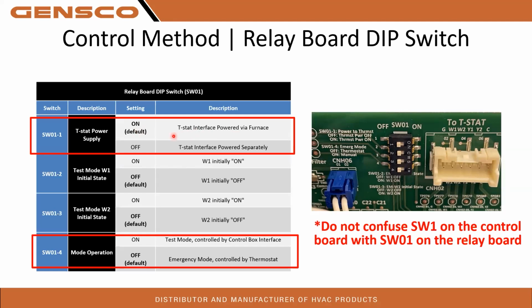These things are supposed to default as the on position from the factory. We have been seeing a few of these coming off from the factory, so you're going to want to make sure that the SW01 on the relay board is turned on. For the SW01 number 4, for your test mode operation, there are some instructions here we'll be going through of how to use that. Again, only used for test mode.